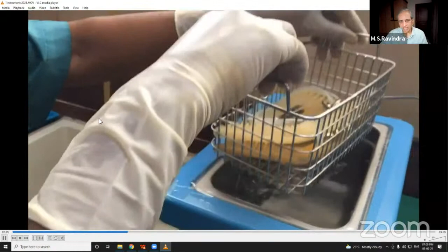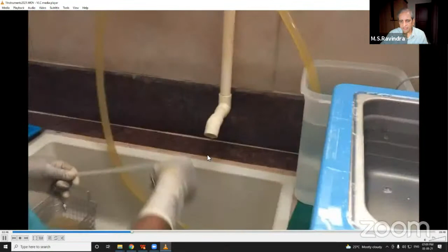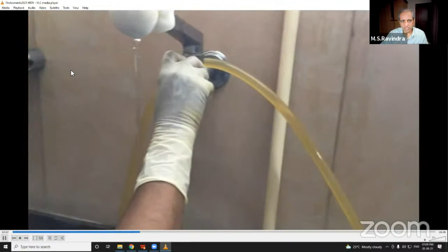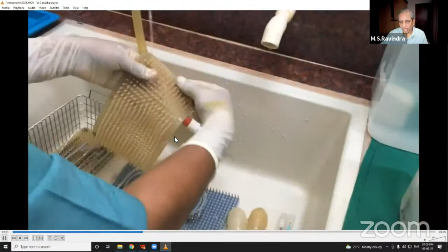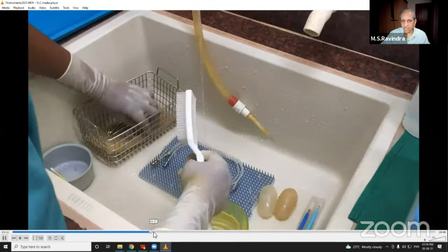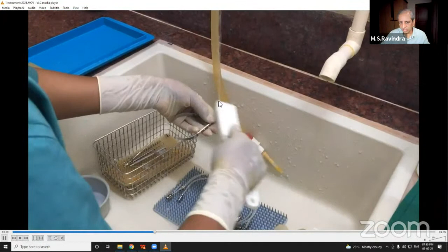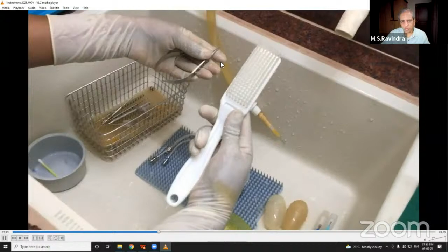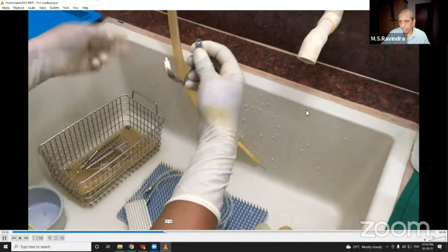This is a separate team which cleans the instruments. This is an area, this is a wash basin, the quartz wash basin. What we have done is this is a submersible tank, submersible pump actually. This is inside distilled water, and distilled water comes. Initially the washing is done with the running tap water. I'll spend a little more time here so that you can go and teach your staff. She cleans the entire thing with tap water, which is not distilled. It has some amount of salinity in it, and every instrument is unlocked and cleaned with a very special soft brush. And whether the instrument is used or not, this process goes on. She doesn't know what instruments we have used in the set. Lock it up. This is the most important.